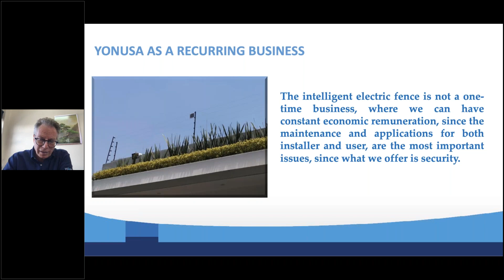Also, you can check things when you go to do maintenance. You just need to check that the battery is okay, that the insulators don't have sparks. You can also check that if you put the wire of the fence to the ground, the alarm goes off, or you can disconnect the equipment from the fence to check that it works by cutting the wire. This is the only thing you can do to test it.